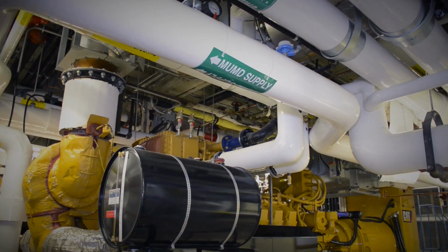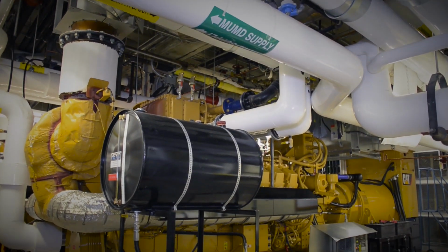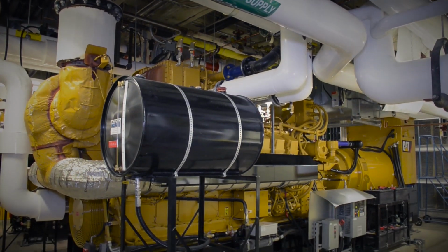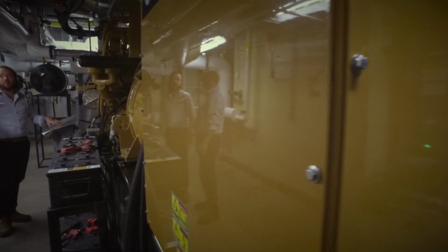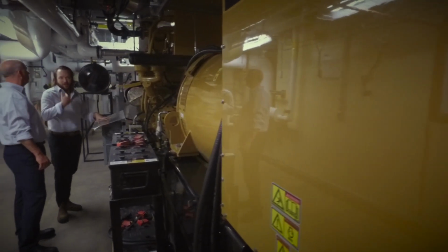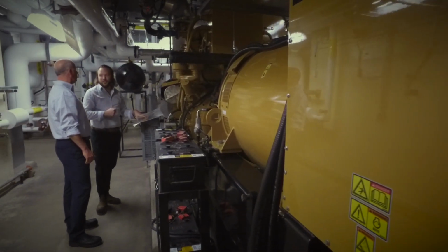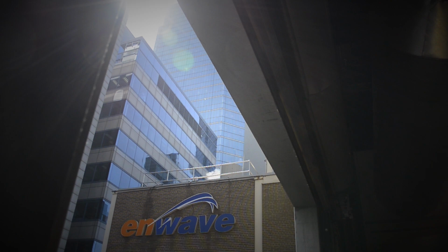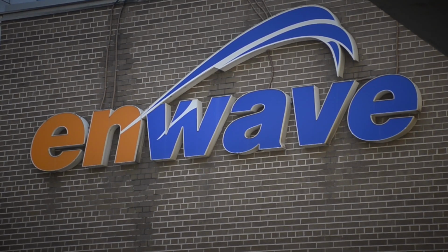A combined heat and power unit essentially generates electricity first, and then harvests the heat out of the exhaust gas, so you're doing two things at the same time versus just running an engine to generate electricity and a boiler to generate steam or hot water separately. You're doing the two processes together, so in theory you're saving on gas and emissions because you're doubling up on a process. A well-run CHP plant will give you about a 33% carbon efficiency gain over running two separate systems.